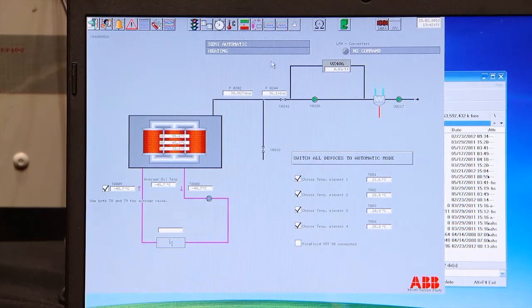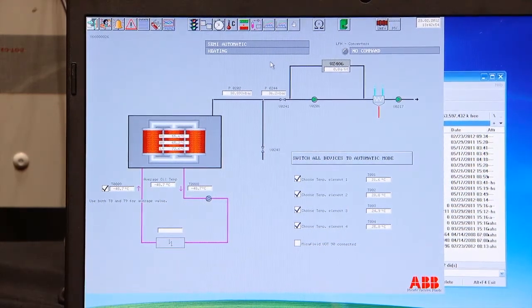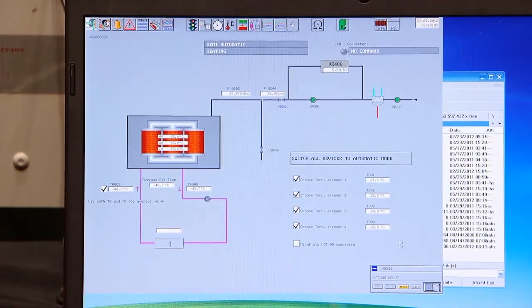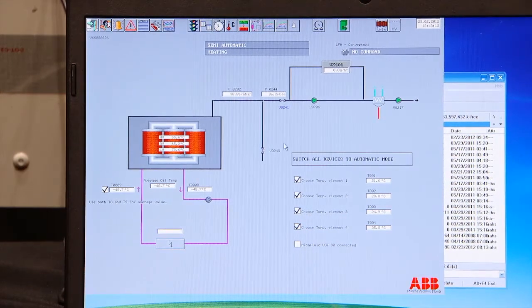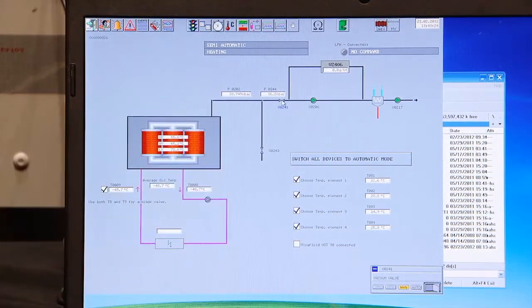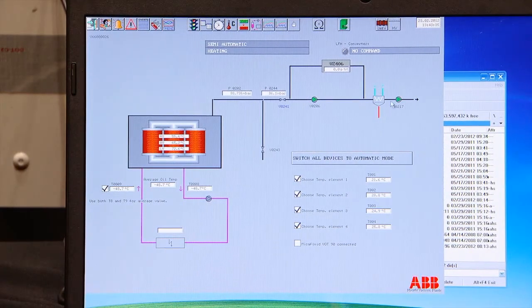What you should do now, before you do this vacuum capacity measurement, is make sure the vacuum valve up here is closed on the transformer. Click on it, put it into manual, and it will close and keep closed. You see the text goes to blue instead of black, and it will be closed. We turned off the roots pump before. We have connected correctly over there, so we can start the capacity measurement directly from here. To toggle that again, you click on the valve, go into manual, and that's it. Because then we shut off the transformer. The vacuum pumps are pumping on a closed valve. The valve will not open from here.